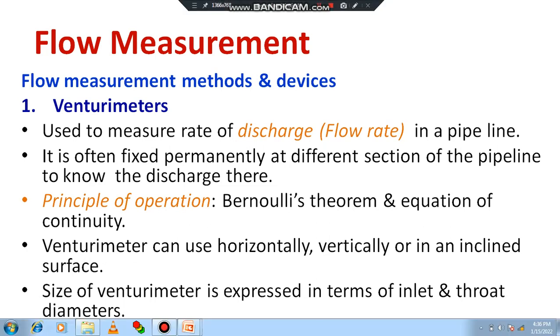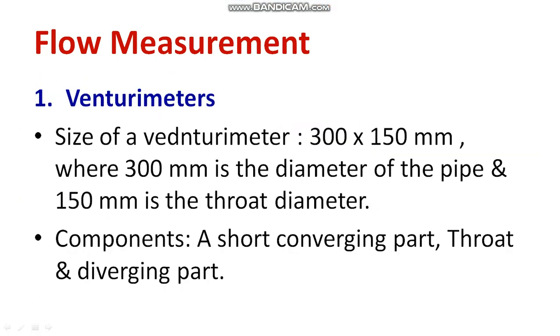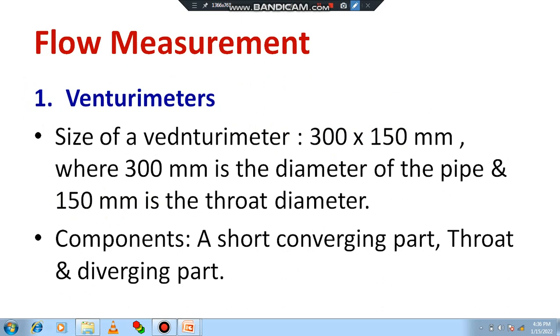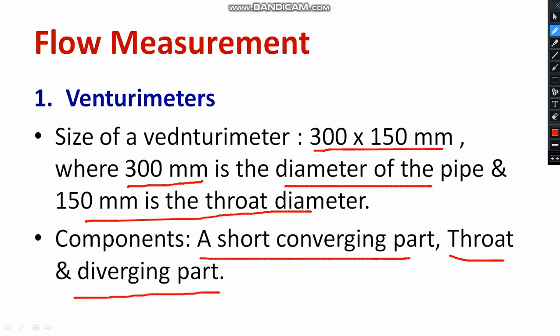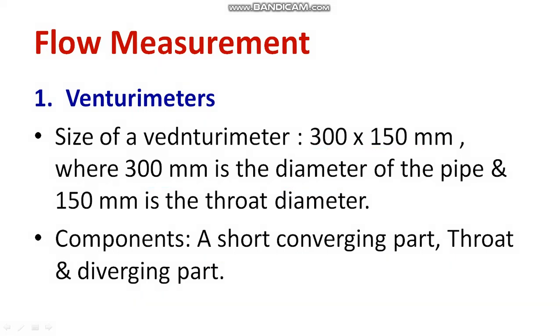Usually, the size of the venturi meter will be 300 and 150 millimeter, where 300 millimeter is the diameter of the pipe and 150 millimeter is the throat diameter. It comprises of three segments: a short converging part, at the middle there is a throat, and at the end part there is a diverging part. I will show you the particular diagram of venturi meter.